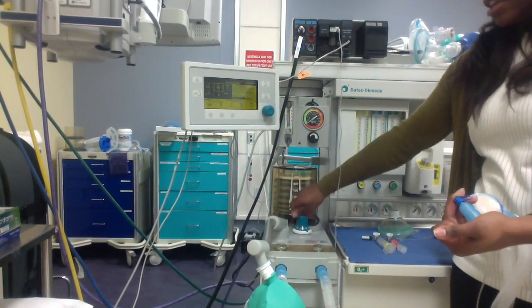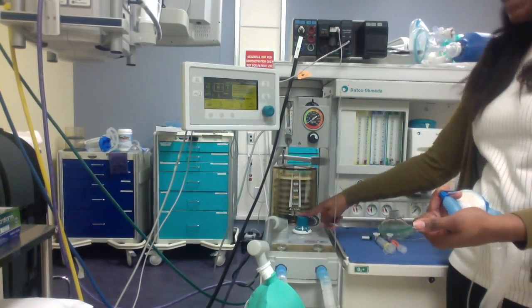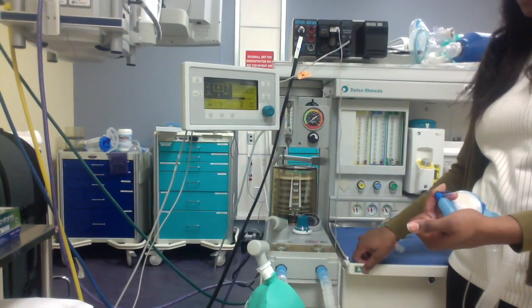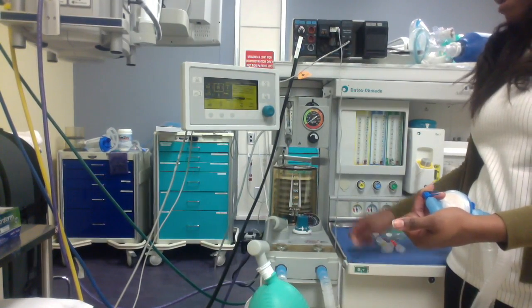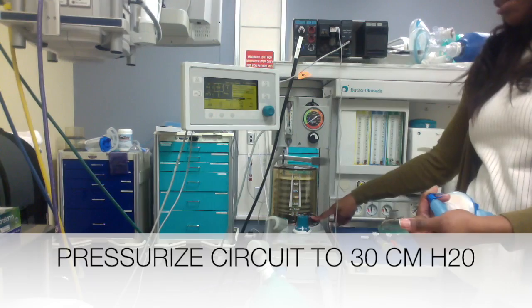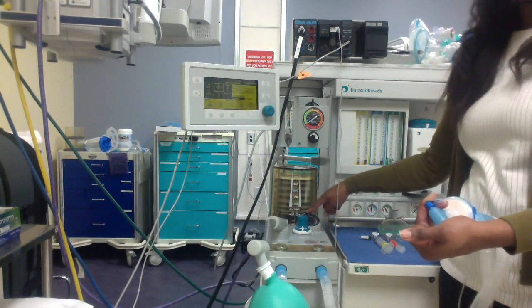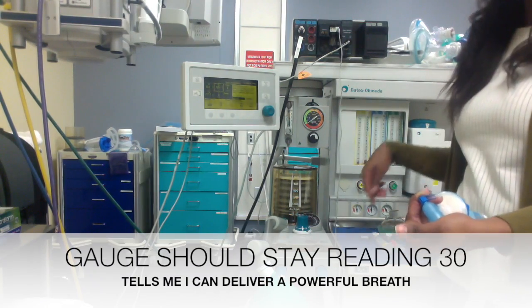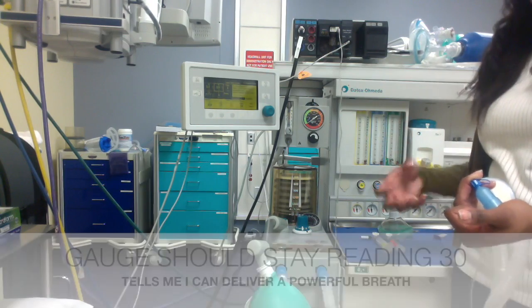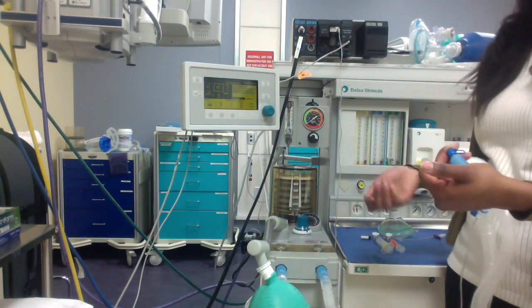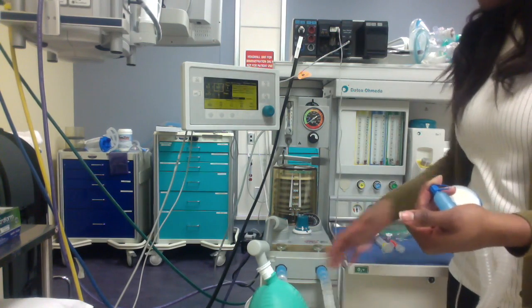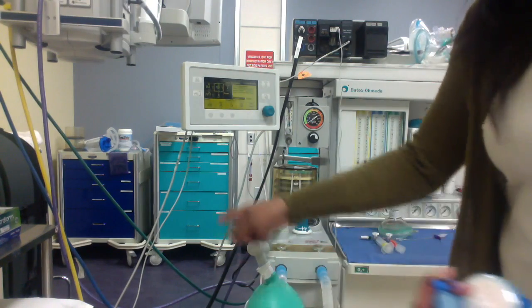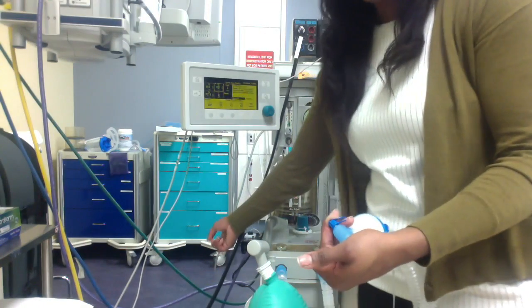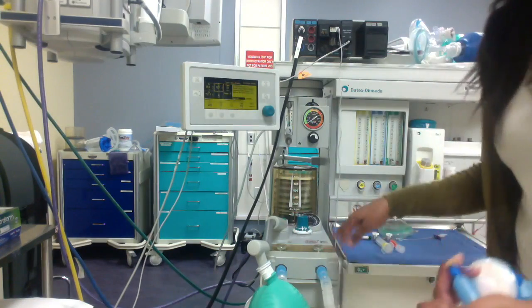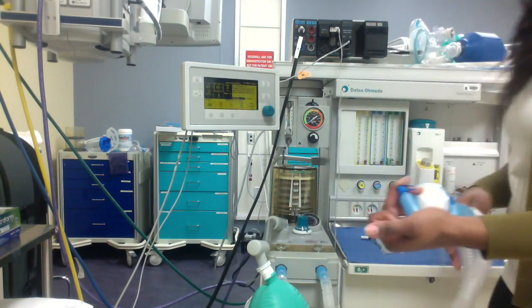So then I'd flip that closed to 70. I would hit my O2 flush again, and on my monitor I want to pressurize it to 30 centimeters of water, and I want to make sure that I can hold that for 10 seconds. That's telling me that I can deliver a nice pressurized breath or PEEP if I needed to. With this filled, I'd also want to come around and check my scavenging system to make sure that balloon was filling as well. That means that this system is working appropriately.